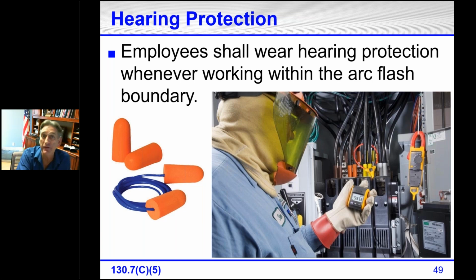If the boundary is 4 feet 5 inches, and you would be within 4 feet 5 inches, you have to wear hearing protection. And I know companies that have it in their policy that whenever they're working in front of live equipment for any reason, they're going to wear hearing protection anyway. And that's a good rule.